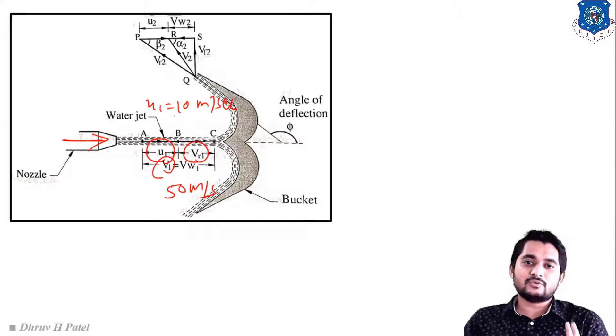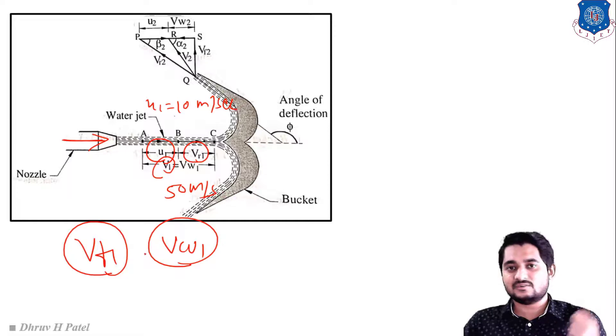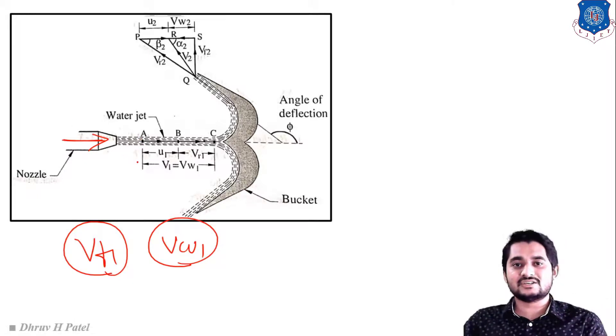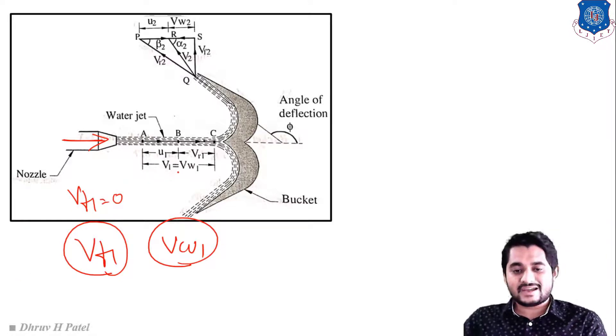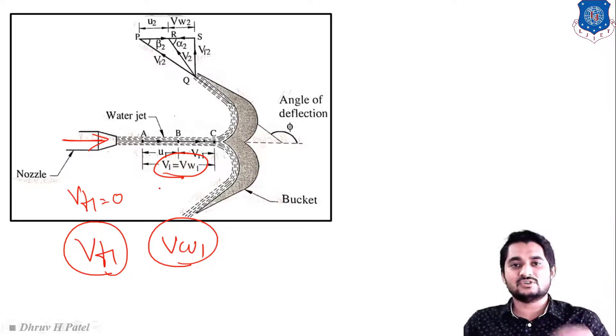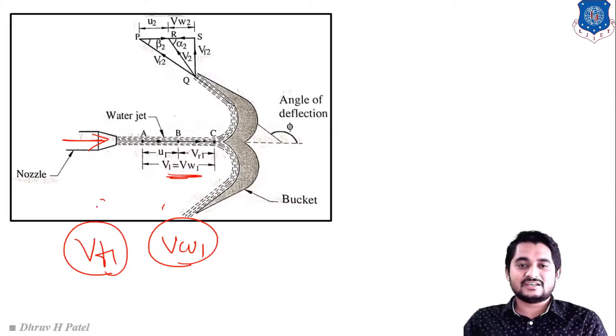The two components of V1 are VF1 (flow velocity, vertical component) and VW1 (whirl velocity, horizontal component). Since V1 is entirely horizontal, VF1 = 0 and VW1 = V1. Therefore at the inlet velocity triangle, alpha1, beta1, and VF1 are all equal to zero.